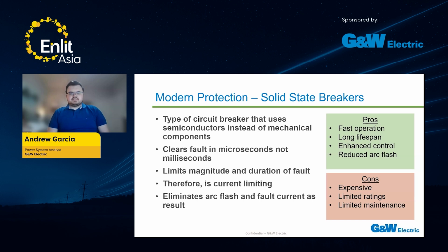However, there's some cons to keep in mind when talking about solid state breakers that may put a damper on all of these pros. One is that they're very expensive. It's a newer technology. And once again, electronics tend to not be cheap. There are limited ratings available, and that's because as you go with bigger and bigger ratings with these solid state breakers, they tend to increase pretty dramatically in size.